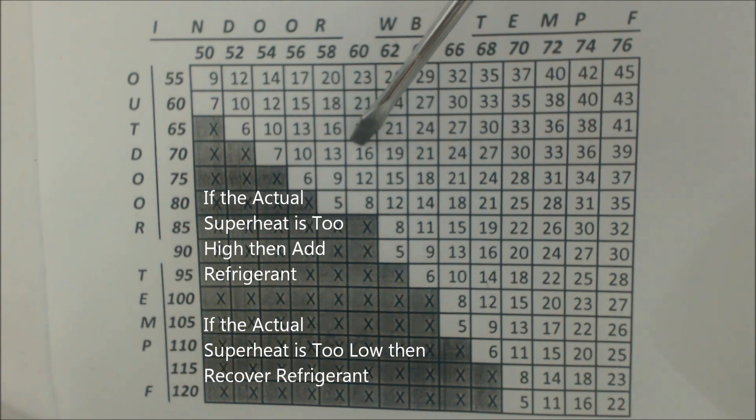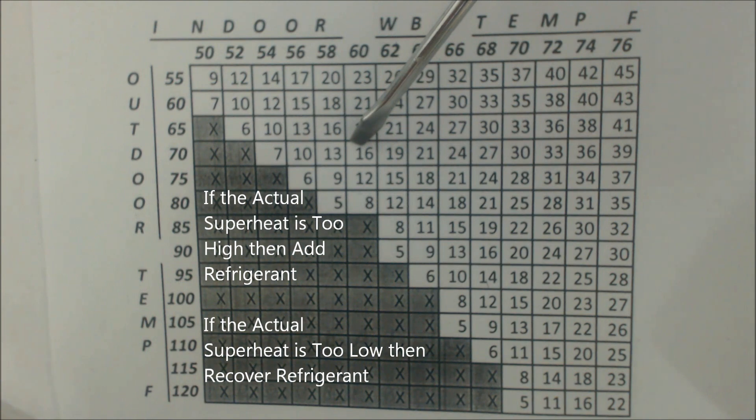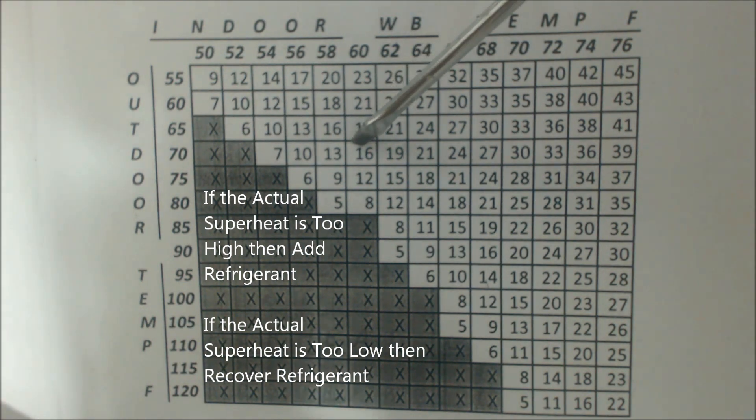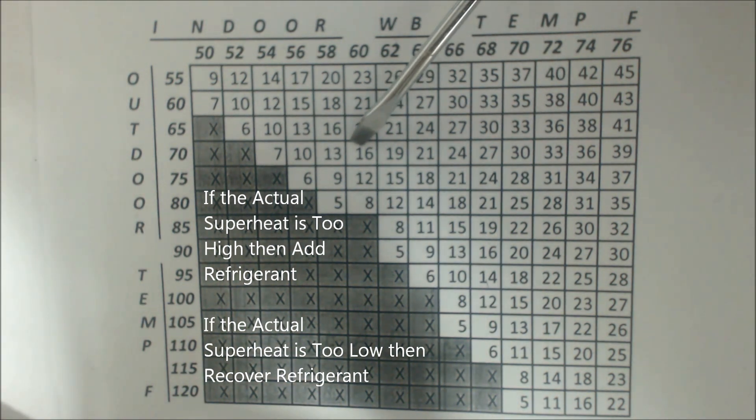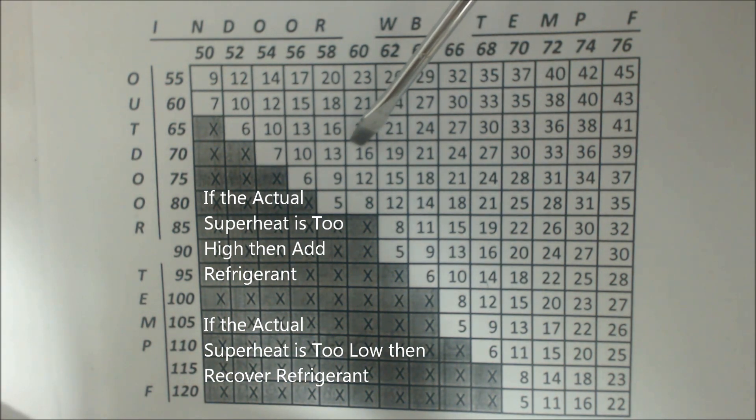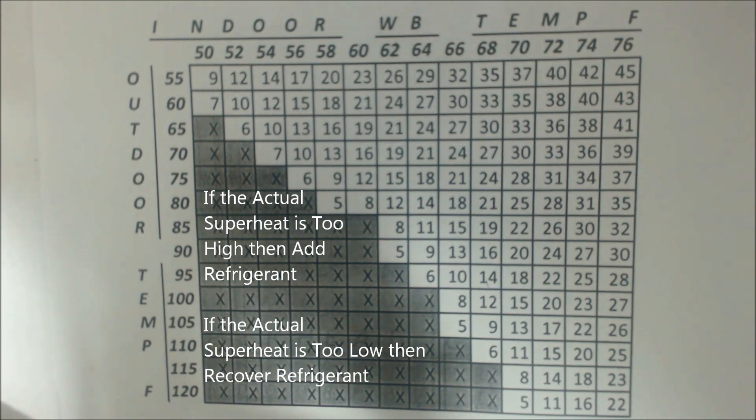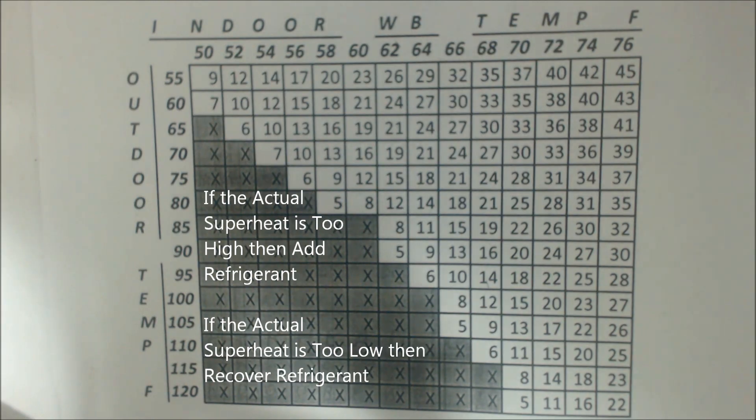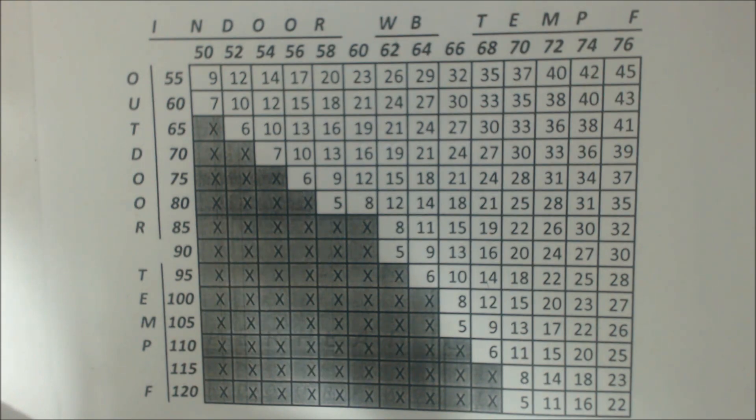If you had 35 degrees of superheat, then that would mean that you're low on refrigerant and you would need to add refrigerant to it in order to lower the superheat. Now there's other factors and such, but let's just say the system is running right and the filters are clean and you have the correct airflow.